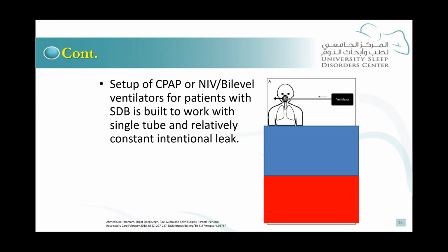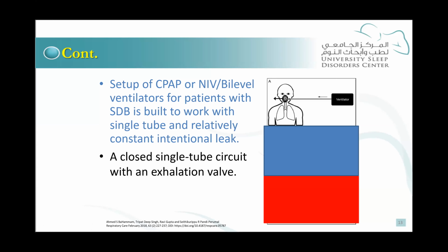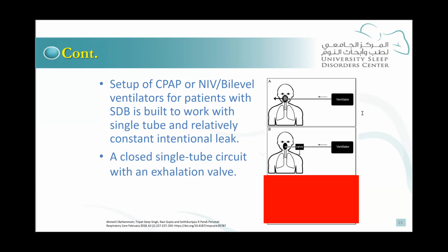So if you look at the setup for CPAP or NIV, bi-level ventilators for patients with sleep disordered breathing, it is built to work with a single tube and a relatively constant intentional leak. If you see my arrow on the ventilator delivering the pressure to the interface, the white opening is what we call the intentional leak. You can do a closed single tube circuit with an exhalation valve. So this is the ventilator delivering through a non-vented mask interface, so there is no opening for intentional leak. It will be in the circuit.